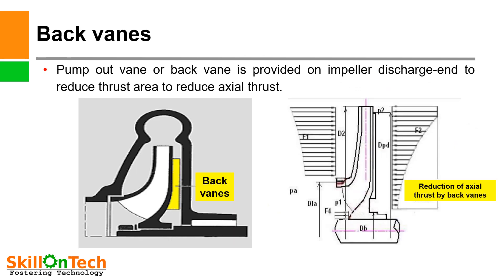Back vanes (pump-out vanes): A back vane or pump-out vane is provided on the impeller discharge end to reduce the thrust area and thereby reduce axial thrust. You can see in this picture that a pump-out vane is provided on the impeller discharge side. By providing a back vane or pump-out vane, the axial thrust is reduced by the area shown in the picture. This measure is also taken in centrifugal pumps and compressors to reduce axial thrust.